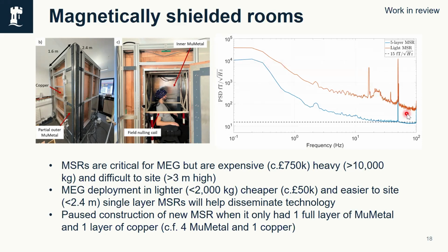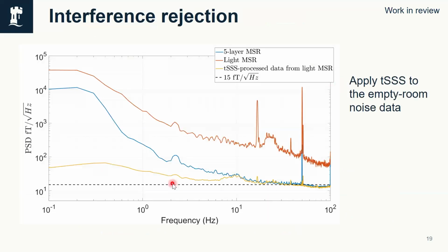We get a really nice noise floor. And if we did the same thing in this light MSR, we get around an order of magnitude increase in the noise, so a lot more noise. If we apply TSSS to this empty room data, though, what you see in the yellow is that we can bring the signal from the red all the way down in the empty room level to be similar to the 5-layer room. So TSSS is working really well at plowing through all this interference, taking it out, and giving us back some MEG data that has a noise floor low enough for us to hopefully see neurological signals.